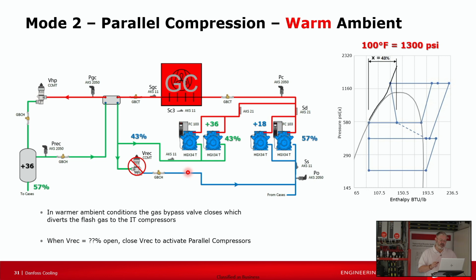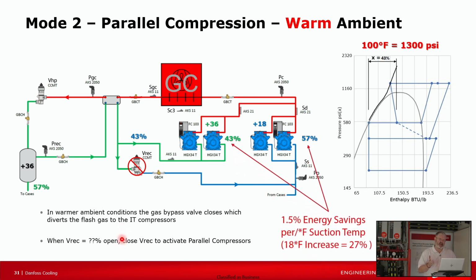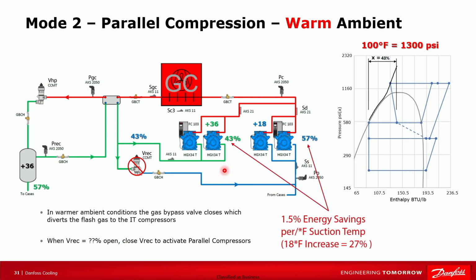The way we get it to do that, there's a set point in our pack controller. The pack controller is wonderful, by the way. You tell it that at a certain percentage of opening for the receiver valve, close and activate parallel compressors. So let's say that was 30%. When we do that on that 100-degree day, we're now servicing that flash gas at roughly 30% better efficiency than we would have on the medium temp.